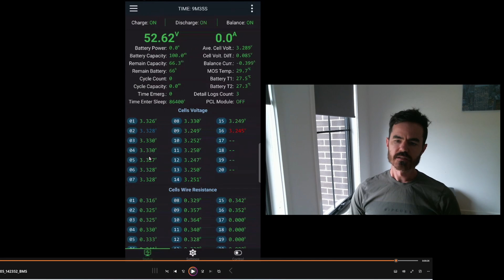So you can see here, the first half of our pack from cell 1 to 8 is sitting pretty balanced, and the second half from cell 9 to 16 is balanced as well, but not between each other, because the first 8 is roughly 3.3 and the last 8 is about 3.250. That's because we had the two separate batteries that I cut in half, so they're not balanced between each other.